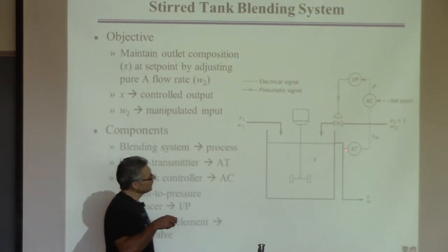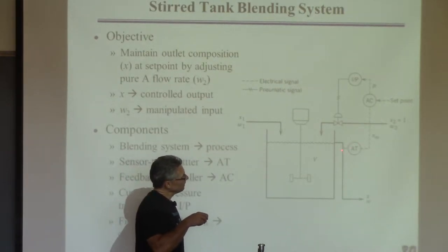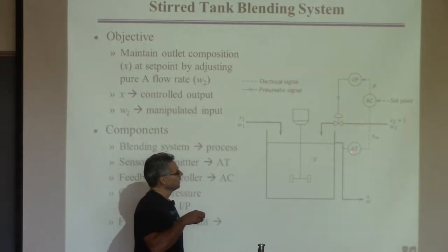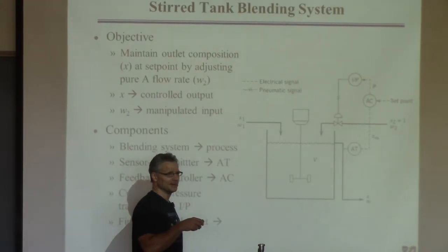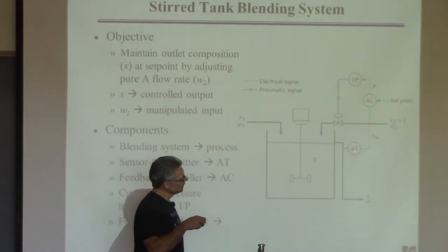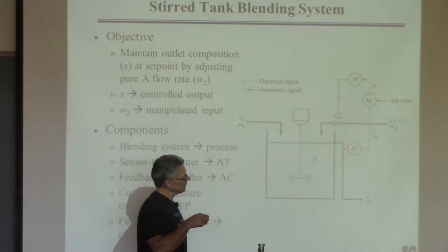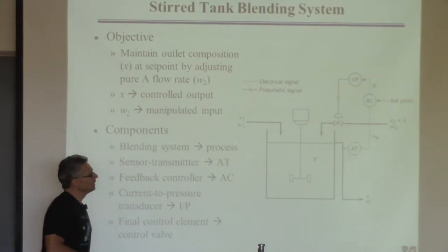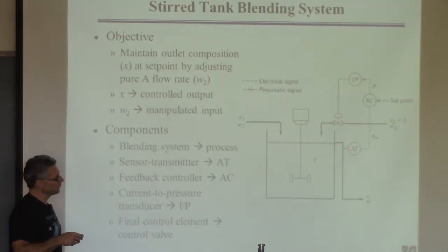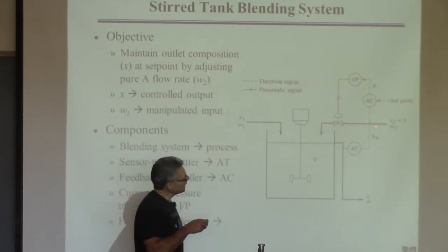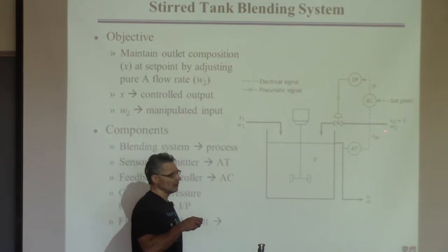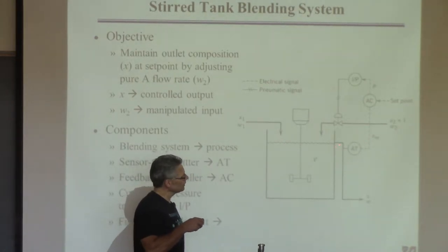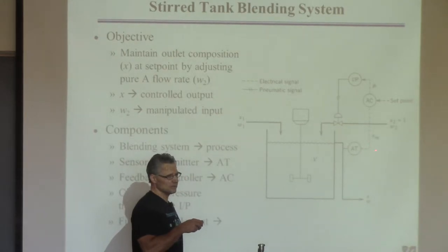When you see a picture like this, there's a transmitter — meaning a measurement is in place. They call it AT for composition measurement. A picture like this means there's a composition measurement, typically done by GC. Then you see a dotted line — a dotted line means this isn't a physical pipe; it's a signal, not a flow.